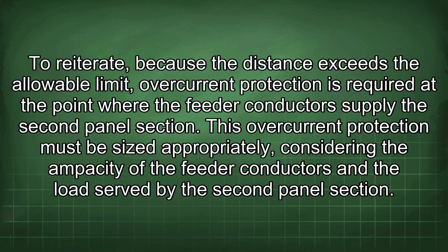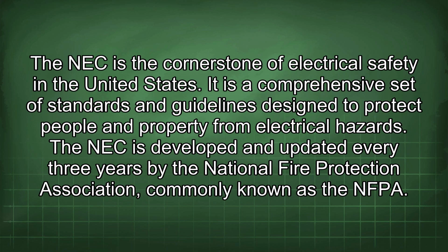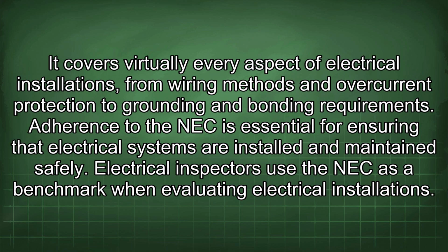This overcurrent protection must be sized appropriately, considering the ampacity of the feeder conductors and the load served by the second panel section. The NEC is the cornerstone of electrical safety in the United States. It is a comprehensive set of standards and guidelines designed to protect people and property from electrical hazards. The NEC is developed and updated every 3 years by the National Fire Protection Association, commonly known as the NFPA. It covers virtually every aspect of electrical installations, from wiring methods and overcurrent protection to grounding and bonding requirements.